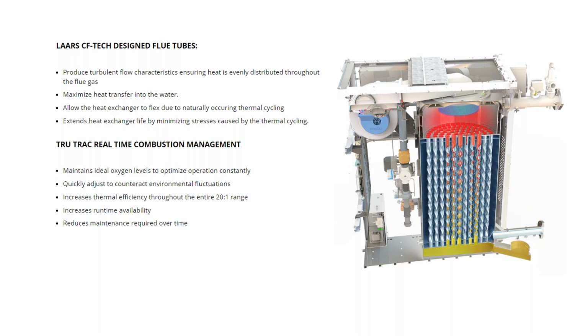These CF tubes are pretty cool. They're like a twisted pinch tube that gives us a lot more surface area on that tube surface, and it makes sure that you have evenly distributed heat throughout the whole flue gas tube. So maximizing the transfer to the water. And flex is a big problem when we have high gas temperatures inside a tube that's surrounded by water. You'll get a lot of thermal cycling going on. So this CF tube design actually incorporates that in the design and allows for more of that cycling. So it extends the life of the heat exchanger by minimizing the stress. TrueTrack O2 combustion is also a big part of this. And once again, it's almost going across the whole line how we're operating on highest efficiency in real world use, not in a laboratory test tube.